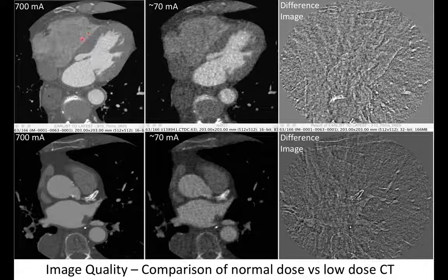Right. If you look at what the reconstructed image looks like, and this goes to that MATLAB thing I gave you to look at signal to noise. What does the reconstruction look like if you use 1/10 of that? This is the image at exactly the same spot. The way this was done, there are two ways. One, we took this data, which has very high signal to noise, and just added noise to it such that it became this data. Added random signal onto the raw data such that it looks like data from 70 mA.